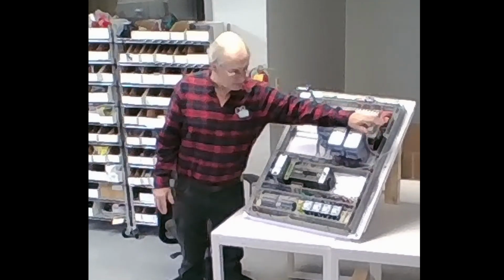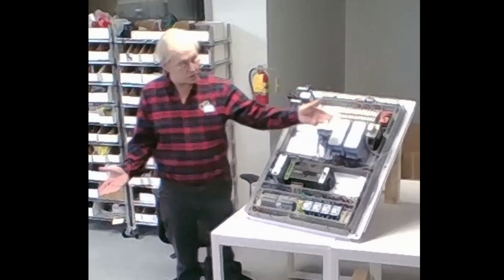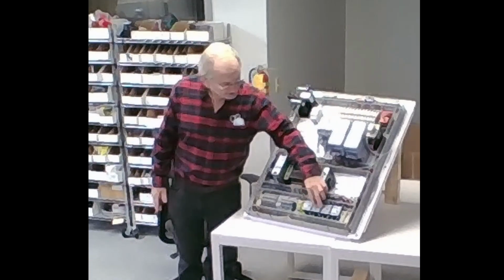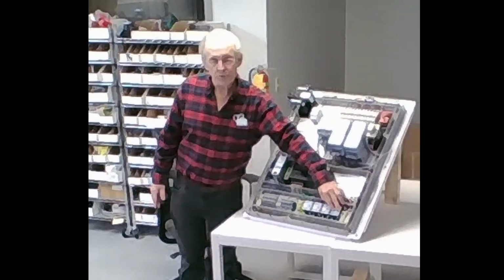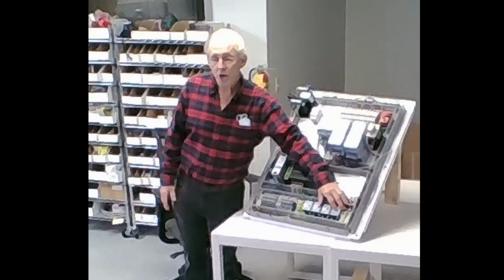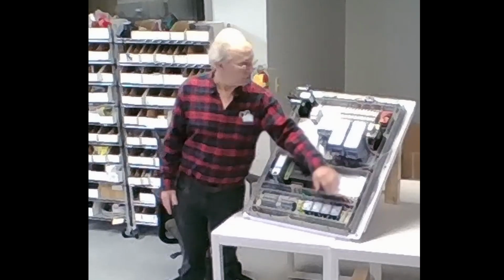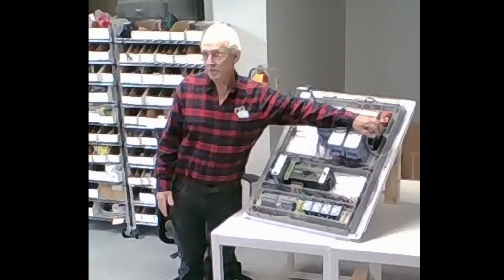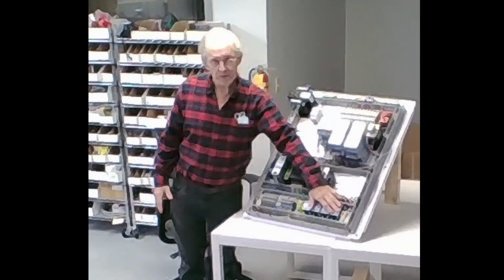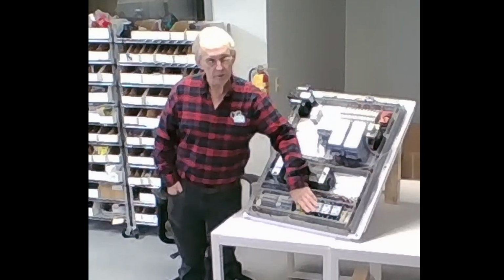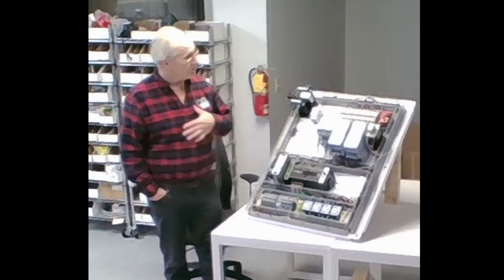So this is a contactor. This is the e-stop contactor. And then we have other contactors. These guys down here are also contactors and do the exact same job. They're just sized for the motor. This one's sized to handle the load of the entire panel, and these are sized to handle the load of an individual motor. Okay?